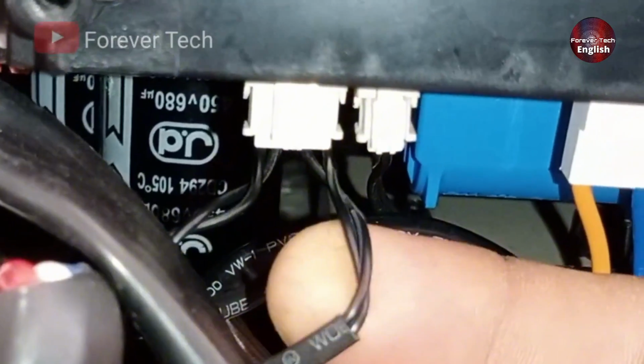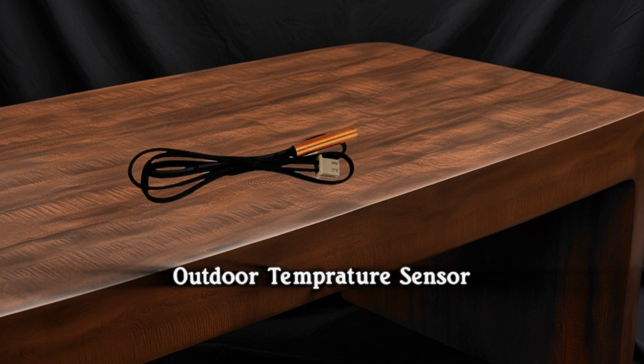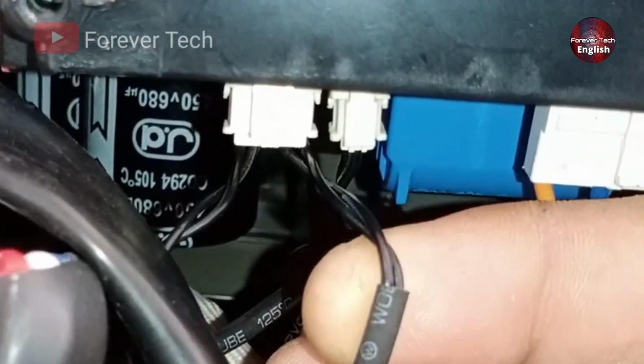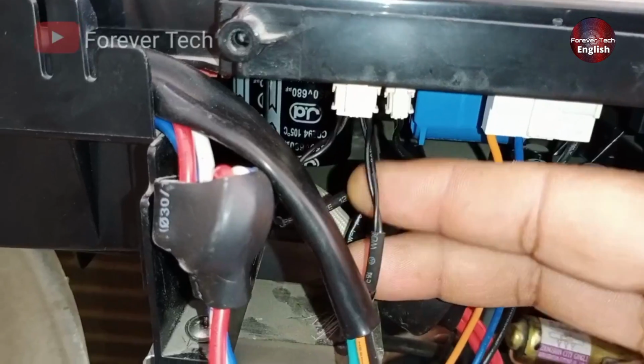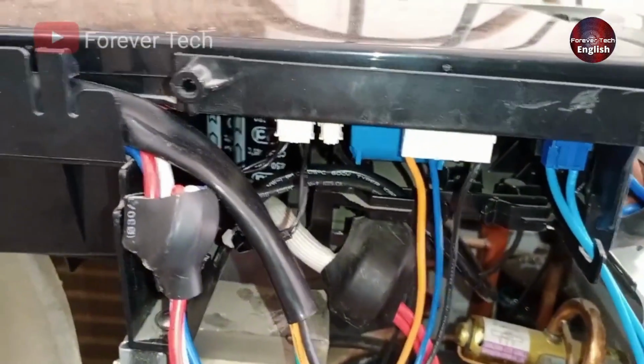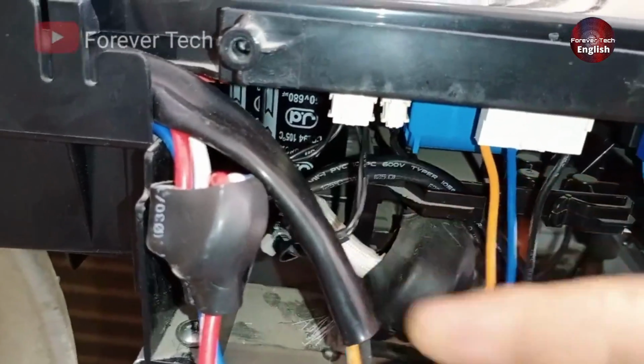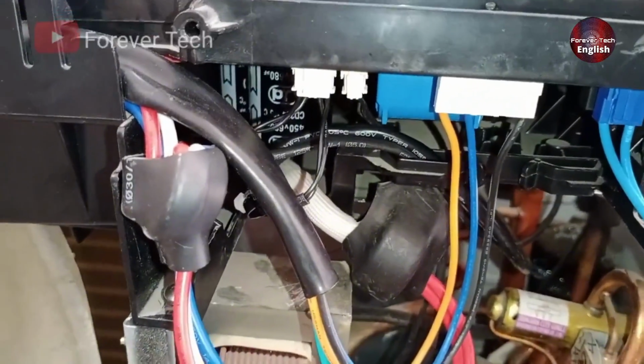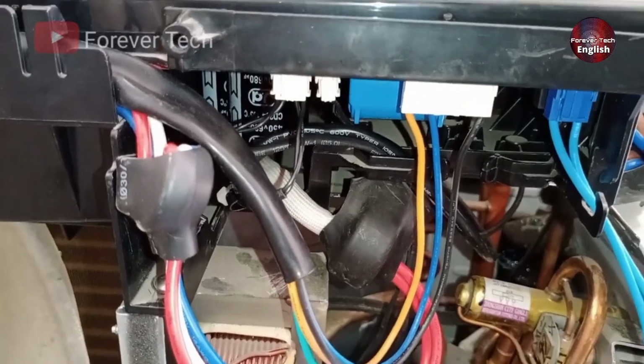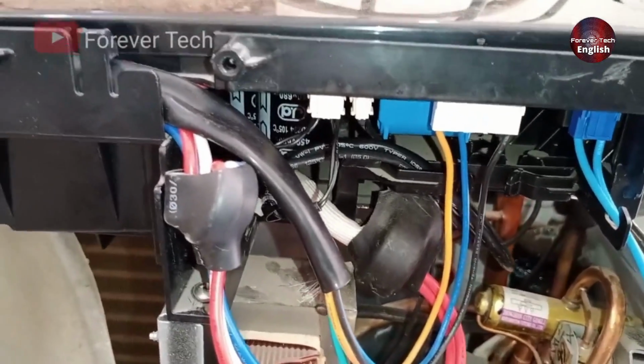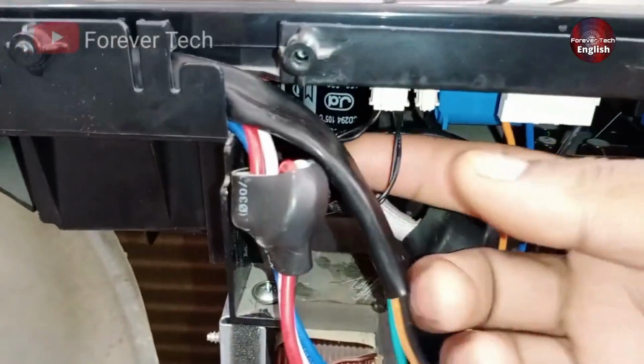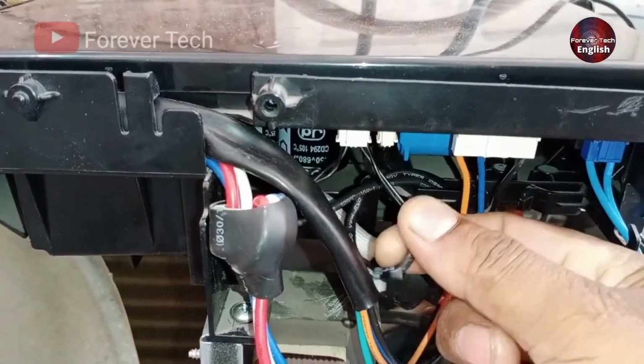The right side sensor in the large connector is the outdoor temperature sensor. If the outdoor temperature sensor is faulty or malfunctions, it will cause the unit to display an E7 error. So if this sensor is faulty or not working properly, it will trigger the E7 error code. You need to check the sensor for any issues. It might be cut, short-circuited, or there could be a problem with the wiring or the PCB.